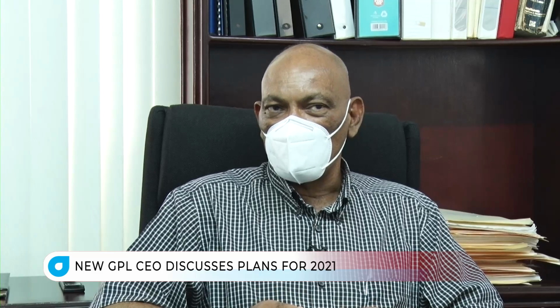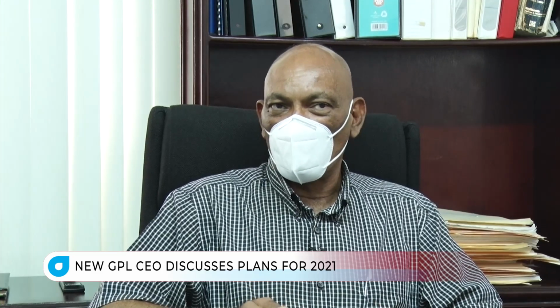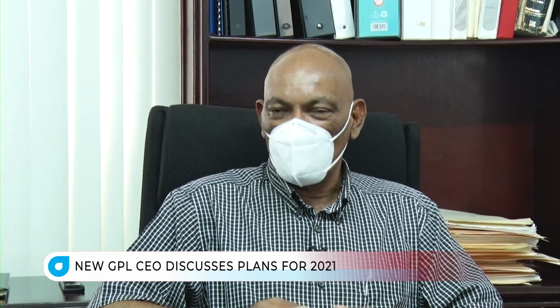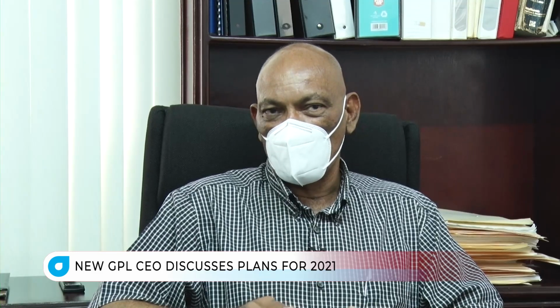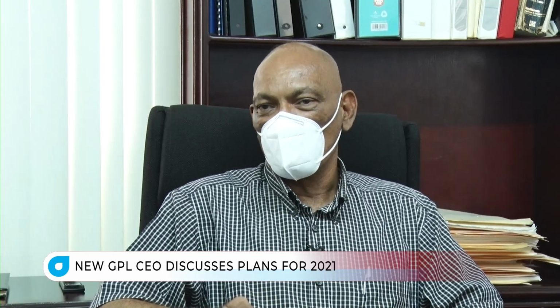In many instances, some of these things are set to operate in extremely short periods of time, about a quarter of a second. So if something were to touch a circuit, a primary line, within a quarter of a second, the power will be interrupted. We are trying to change that to allow for some more delay for transient problems to be cleared before the power is taken off.